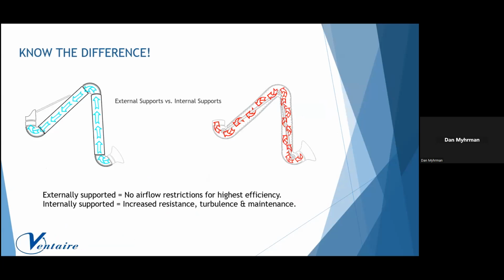Last slide I mentioned that with the SIFA, all the supports are outside the airstream. The diagram on the left shows a simulation of the air through the fume arm with all the supports outside the airstream. The right side shows what it looks like for internally supported fume arms. Increased resistance through the fume arm on internally supported ones, turbulence, maintenance. All those dirty fumes and particulate making their way through an internally supported arm get caked up on those internal supports, so they'll have to be taken apart and cleaned, adding quite a bit of maintenance, plus resistance to the system.